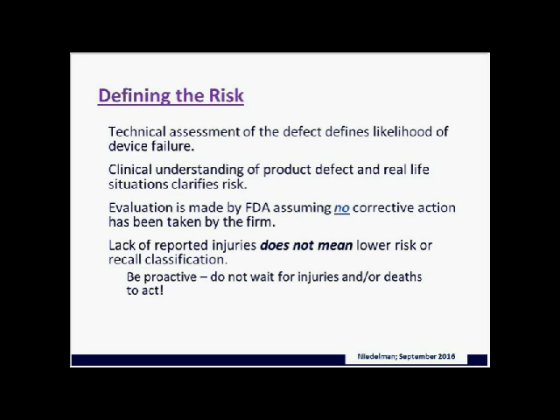Some of the challenges associated with Class 1 recalls that we've seen over time: issues where manufacturers can disconnect. Firms say the defects are easily recognized by the physician. Workarounds are proposed and are either being done by surgeons or healthcare practitioners. They know how to deal with this. It's easy as can be. But again, going back to the earlier comments, that could be distracting the physicians. Other systems provide backup, so it's not as catastrophic. You have a backup system. If this fails, we have an alternative. Or there are alarming situations. Yeah, but we don't pay attention to alarms.